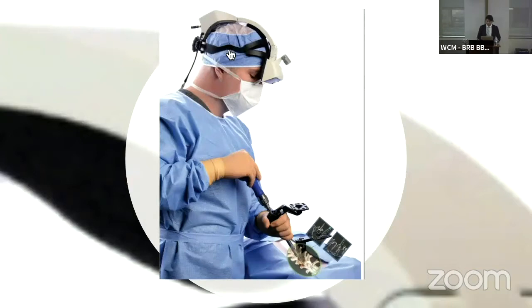Our tracking camera is directly mounted on this headset along with a surgical headlight, and the entire processing power is built into the headset. We've miniaturized an entire surgical navigation workstation into a small headset, giving us improved accuracy and position — because one of the main variables in navigational accuracy is the distance from the tracking camera to the reference frame and your tool. The camera sitting directly over the patient opens the door to a whole new host of possibilities: high-resolution tracking cameras doing surface-active matching registration, live surface match tracking to see active movements and deformity corrections, using AI and machine learning to guide osteotomies, decompression, soft tissue and CT overlays so you can see neural structures and guide tumor resections.